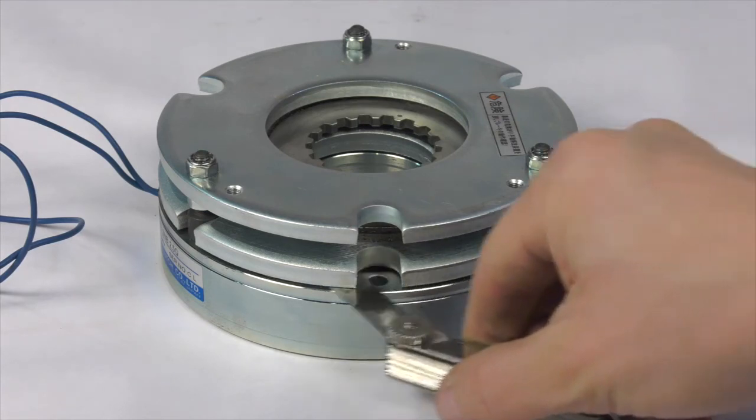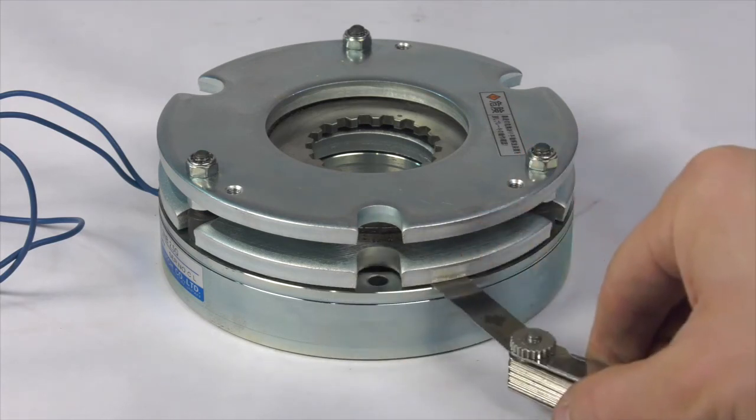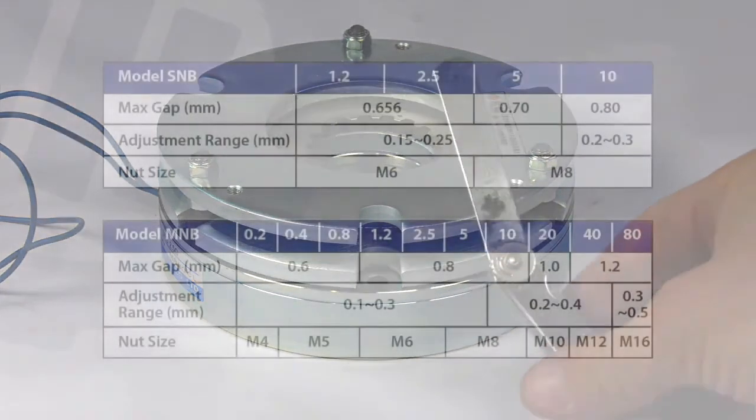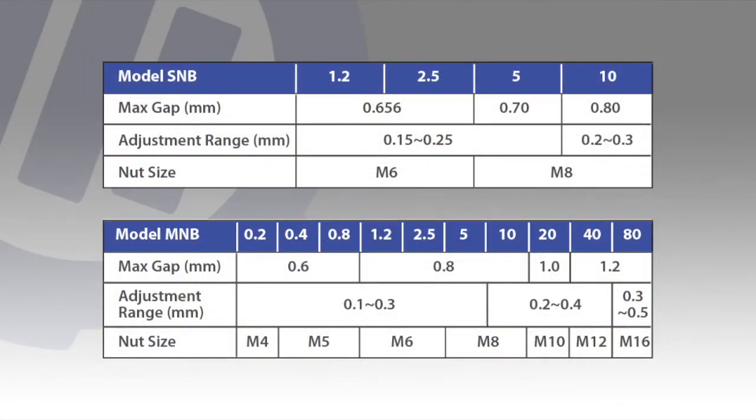Make sure that the air gap measured at all three adjustment points is within 0.5 millimeters of each other. Specific gap and adjustment range is as shown.